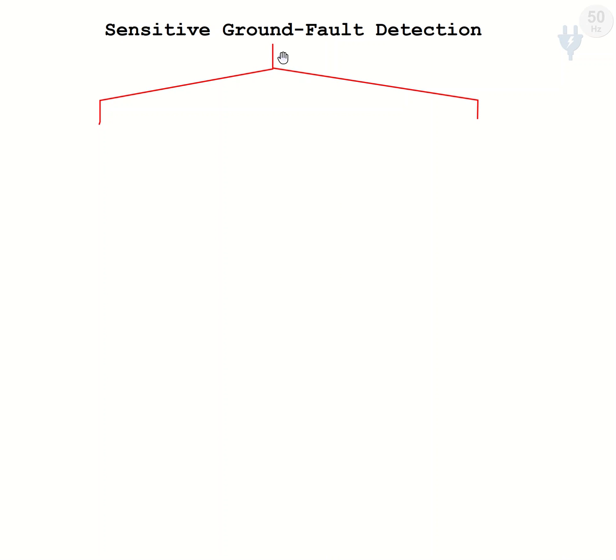Now let's understand how many types of sensitive ground fault detection exist and the knowledge behind each one. According to fault direction, whether forward or reverse, we have two methods. One detects forward or reverse direction by the directional method. Another is non-directional, where our system will detect any fault and may trip or pick up according to our selection.